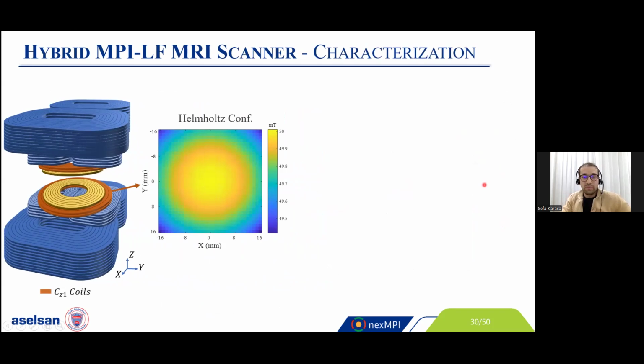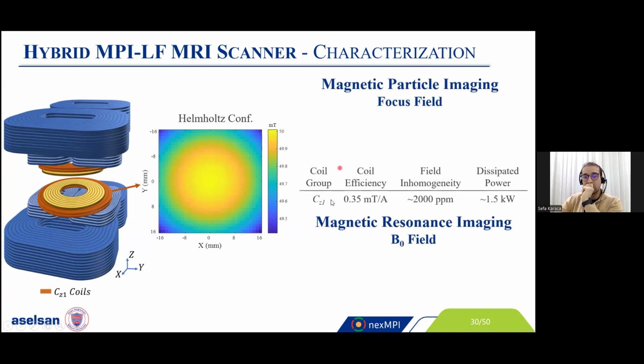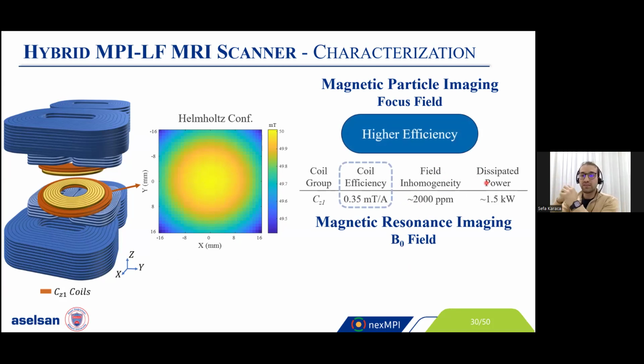So I would like to talk a bit more about the CZ1 coils. As I said before, we use them in the Helmholtz configuration for both MPI and MRI, generating the focus field of MPI while generating the B0 field of MRI. So this is our field map. We experimentally measured this field map, and these are the coil efficiency and the field inhomogeneity of our coil. In the case of MPI, we are trying to generate the focus field, and this means that if we have higher coil efficiency, we can scan a larger field of view, which is our main design criterion, because this coil group was initially designed only for MPI, with a design which maximizes the efficiency.